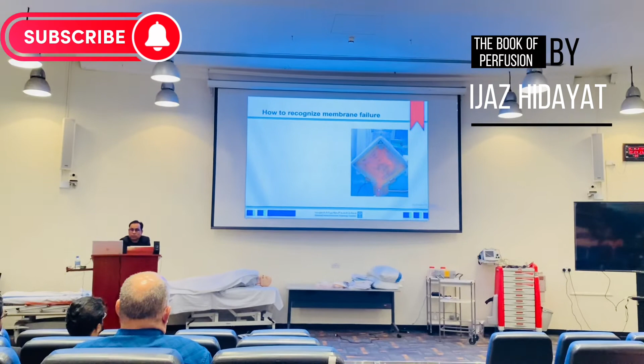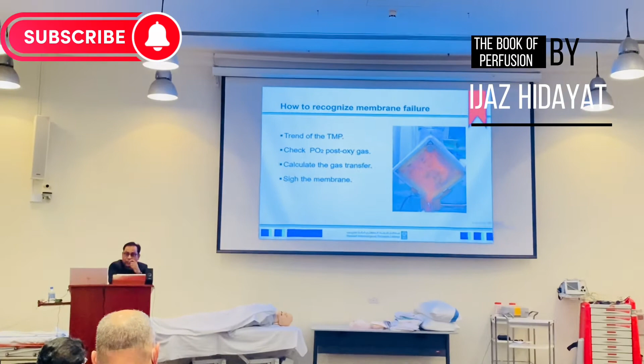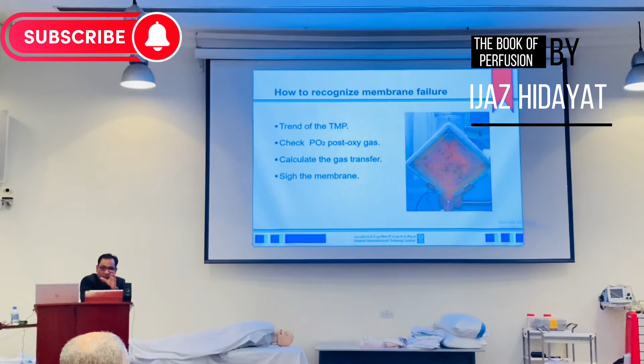So what you have to do to prevent this trend of delta P continuity: on a daily basis, you have to check the post-oxygenator PO2 of the patient on every shift, not once a day, and then calculate the gas transfer, whether the oxygenation is according to the flow or not. If it is less, then you have to change it, and then you have to do the sighing of the membrane. The sighing of the membrane is needed because when you are running the machine continuously, there is a chance of condensation in the membrane, and that is going to block your membrane, and the oxygen can get stuck and not diffuse properly.